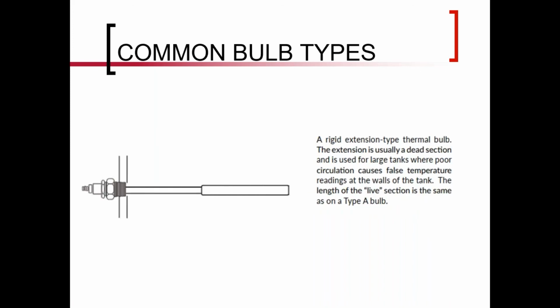And then just an extension type. So in some cases, companies don't want to measure the temperature right at the edge of the wall. So this is kind of a dead zone on this type of bulb, so that the actual temperature sensing part is further into the tank. Sometimes out at the wall, it's a little different than inside, and some people prefer to have the actual temperature inside.